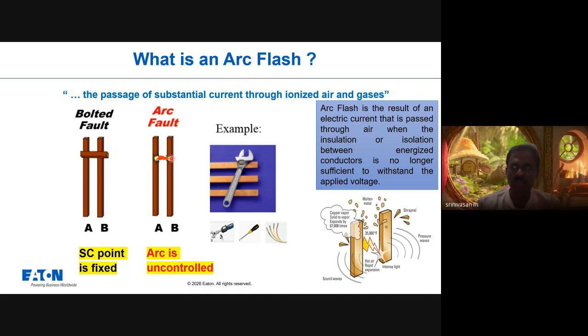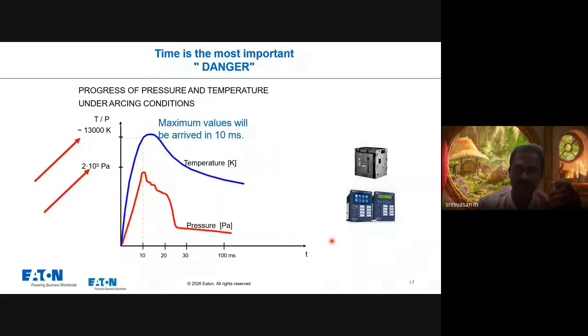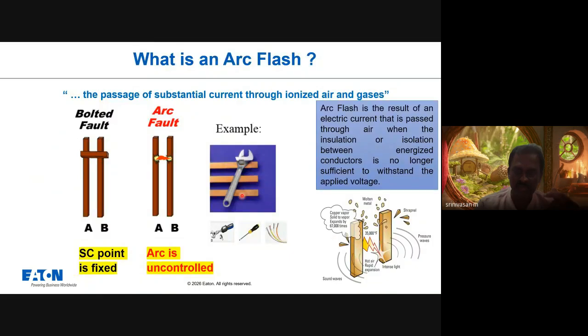On the other side, suppose in a live switchgear, by mistake, a torque wrench or spanner or wire falls between the phases, which creates an arc. This is a high impedance arc, and it is uncontrollable. When such a high impedance arc happens, it reaches an enormous temperature, with melting of the parts. Parts can also eject from the bus bar or bus bar supports, and it produces a very intense light and very hot air expansion, all happening very quickly, before the blinking of an eye. So this is a very important point.